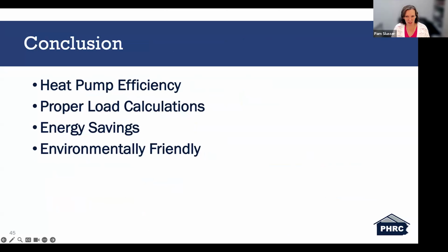So in conclusion of all of this, as I wrap up, heat pumps are highly efficient. They're flexible, they're sustainable. They have sustainable heating and cooling options, especially for Pennsylvania in our varied climates. Whether we're talking about air source, ground source, or ducted mini splits, the key is selecting the right system for the home that it's going to be installed in, for the client and the regional demands. We explored how proper sizing and installation based on Manual J, D, and S calculations can make or break performance. We looked at the impact of energy ratings, ductwork installation, maintenance, all of that, how all of it goes into shaping both comfort and energy bills, better energy savings down the road.